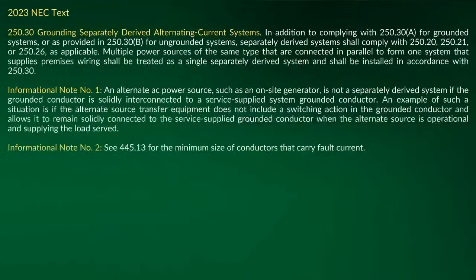Yeah. Now, this is interesting because if I go look at 250.35, it gives you the options where you talk about a separately derived system and a non-separately derived system. And it talks about how you go about classifying a separately derived system for 250.30. But if I have a non-separately derived system, looky there, then they start telling you how to size a conductor using 250.102(C). Well, why is that? When you start looking at other sections, this can cause a problem. And personally, I see what Justin's saying.